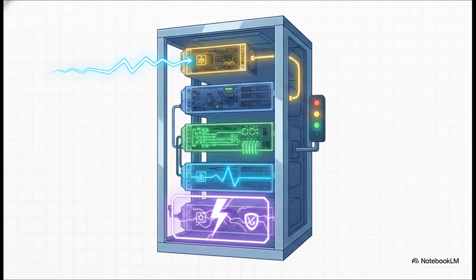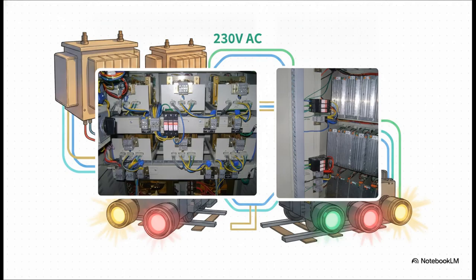surge protection. If we look right inside the AC distribution panel, you'll find these heavy-duty step-down transformers. They take that 230-volt AC from the inverters and step it down to a constant 110-volt AC supply. And that is the exact power feed that keeps those vital signal lamps glowing brightly and track circuits functioning, totally regardless of what the main power grid is doing.